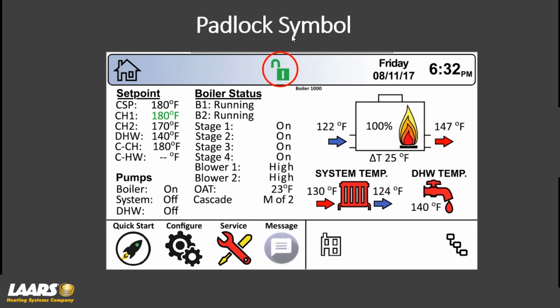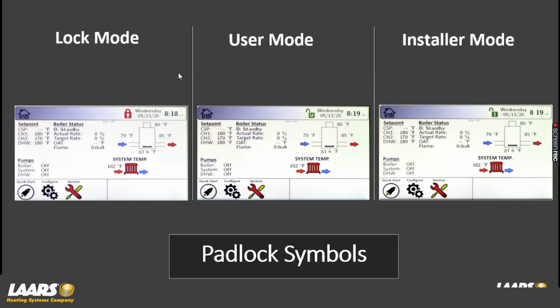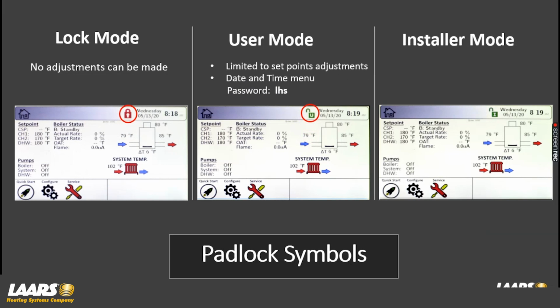Now, I've highlighted the padlock symbol here. We're showing a padlock that's unlocked with the letter I for installer. I just want to talk about this because when we get into the combustion setup video and service video, you'll have 3 options here. So lock mode, the padlock would be in red and locked, and obviously no adjustments can be made. Leaving the factory, you'll be in user mode. So the letter U appears in the padlock and it's unlocked. The only thing you can really change in user mode is a set point, maybe the date and time that's up here. So you can get in and change set points, etc.